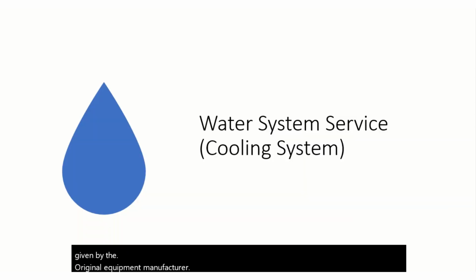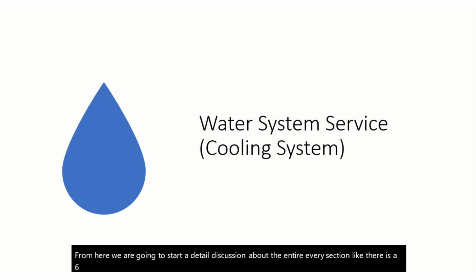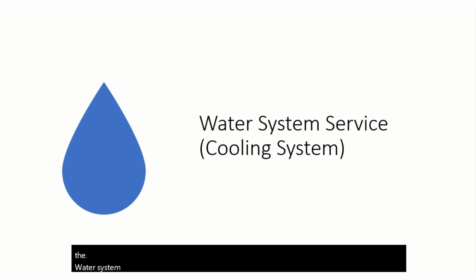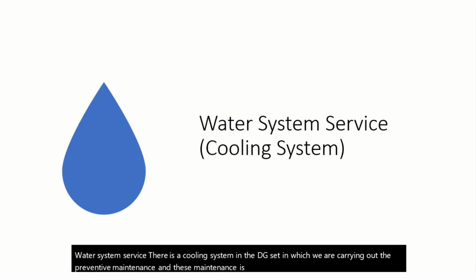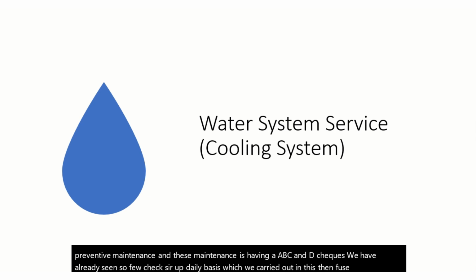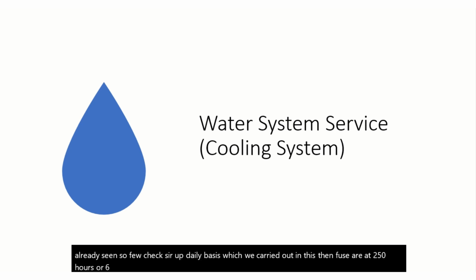Now from here we are going to start a detailed discussion about every section. There are 6 different sections in the DG sets which we have seen in the previous slides, in which the first one is the water system service. There is a cooling system in the DG set in which we carry out the preventive maintenance, and this maintenance has A, B, C and D checks, which we have already seen. A few checks are on a daily basis, then a few are at 250 hours or 6 months, and then annually, and then every 2 years.